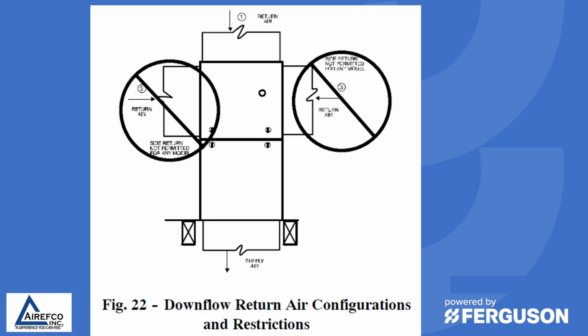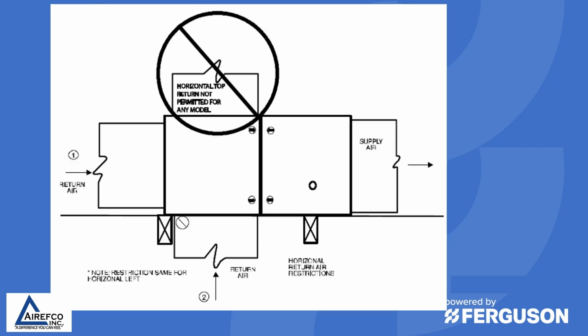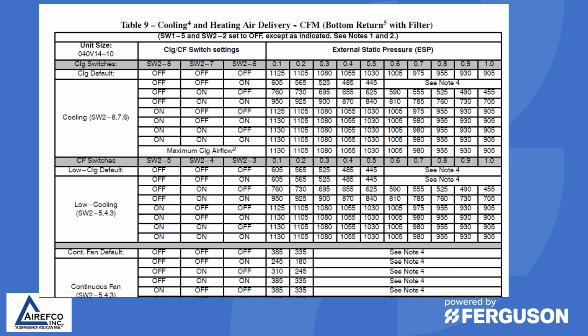This installation instruction states that in a downflow position, the only configuration of ductwork for return air that is recommended is from the bottom of the furnace itself. You cannot have any side returns. And this instruction states that in a horizontal application, a horizontal top return is not permitted for any model. On many furnaces, the CFM being delivered is set up by dip switches.